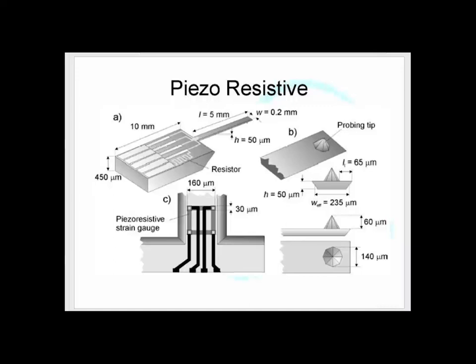Piezo-resistive pressure sensors are excellent. They're very susceptible to other things that might do squeezing, like temperature, which might squeeze the piezo. Vibration might cause bad readings, because vibration looks like a whole load of pressure coming and going.